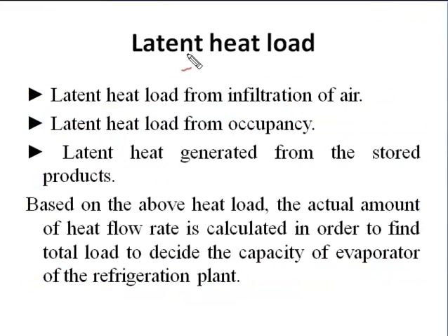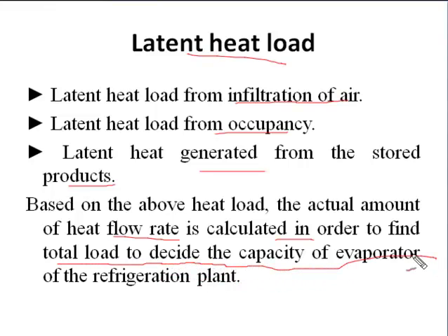This is the latent heat load in cold storage. Here: latent heat load from infiltration of air, latent heat load from occupancy, and latent heat generated from the stored products. Based on the above heat loads, the actual amount of heat flow rate is calculated in order to find the total load to decide the capacity of the evaporator of the refrigeration plant used in cold storage.